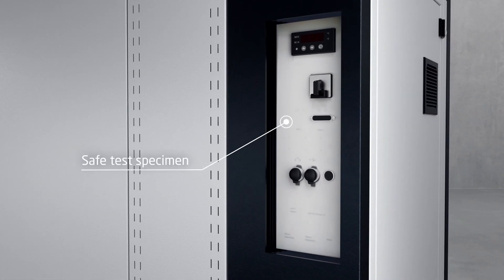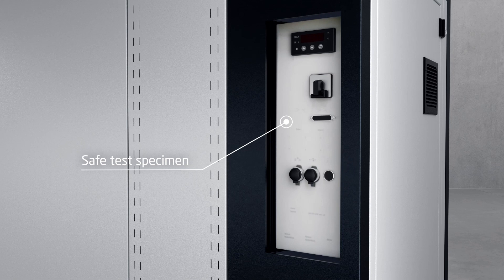In the main switch panel, in addition to the main switch, you will find the interfaces such as USB and Ethernet, the safety temperature limiter, the temperature limiter to protect the test specimen, and other optional connections. The test specimen protection runs via an independent adjustable temperature limiter whose temperature sensor is installed in the test chamber. The test material shutdown for heat-emitting test specimens runs via a potential-free contact.